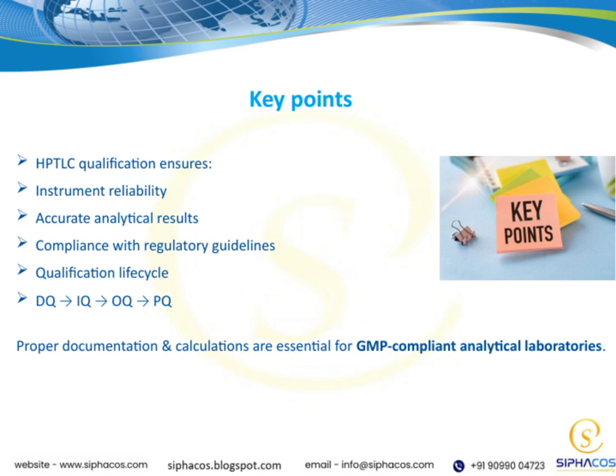Now, moving to the qualification lifecycle. This is a structured process that begins with design qualification, or DQ, where we define what we need. Then we move to installation qualification, IQ, confirming the instrument is installed correctly. Followed by operational qualification, OQ, to verify it operates as intended, and finally performance qualification, PQ, which proves it performs consistently under real-world conditions.